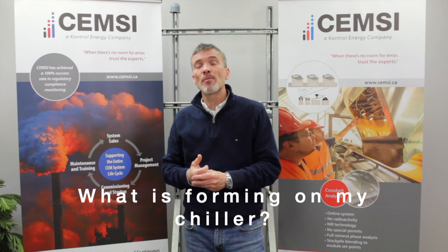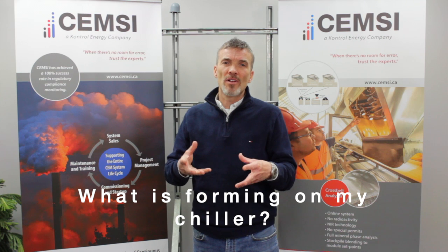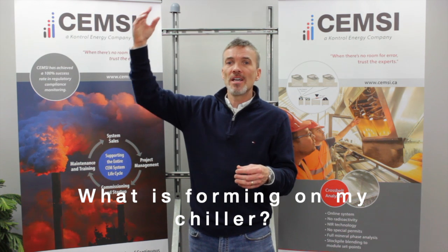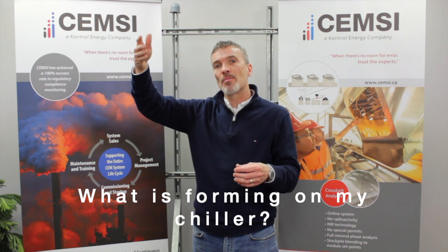Quite a common one is, a customer calls up and says, I've got a chemical salt forming in my chiller. And why it's so critical at the chiller is because, if you're using a heated probe and heated sample line, the chiller is the first point where that gas starts to cool down.